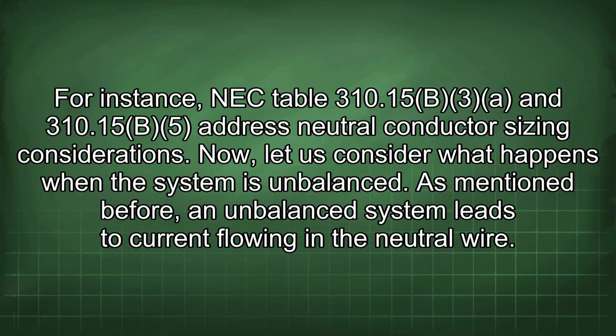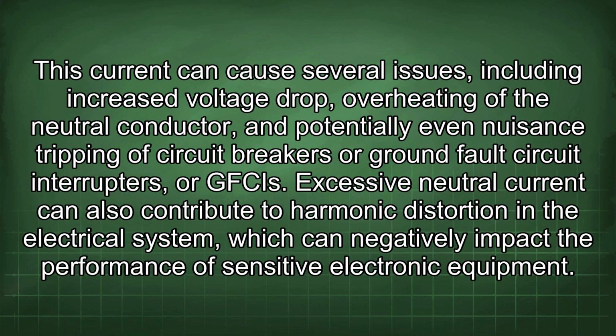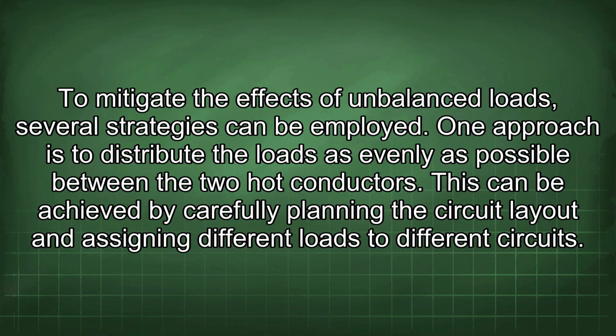Now let us consider what happens when the system is unbalanced. As mentioned before, an unbalanced system leads to current flowing in the neutral wire. This current can cause several issues, including increased voltage drop, overheating of the neutral conductor, and potentially even nuisance tripping of circuit breakers or ground fault circuit interrupters, or GFCIs. Excessive neutral current can also contribute to harmonic distortion in the electrical system, which can negatively impact the performance of sensitive electronic equipment.